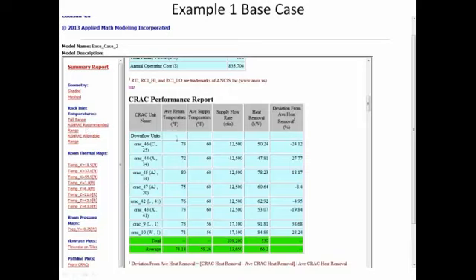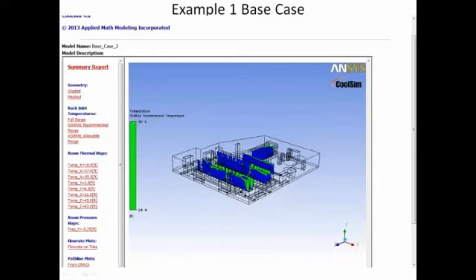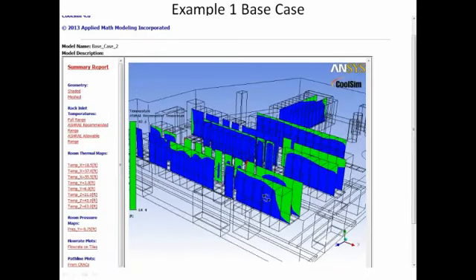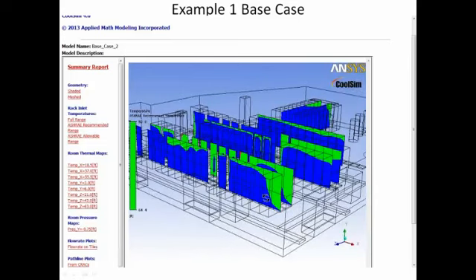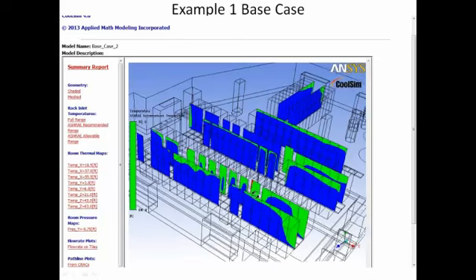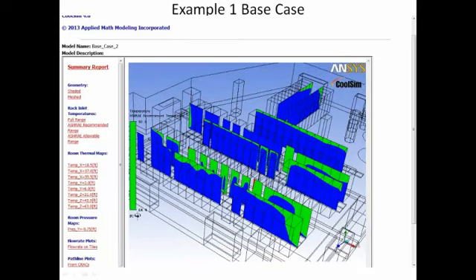Now, to see that, we have a bunch of other plots here, the most important of which, Magnus, is one we've added recently to the solution, and it's called the ASHRAE recommended range. So these are rack inlets here that I'm looking at. Again, I'm doing it all inside of PowerPoint. These are the rack inlets, and I'm looking at temperature variation with respect to this green band. 64 is the low, 80.6 is the high, and we'd like everything in the room to be in that band. It means we'd be conforming perfectly. But the fact that our RCI low is less than 0 means that we're well under temp, and you can see it here in blue. So the combination of the summary report plus these two plots.